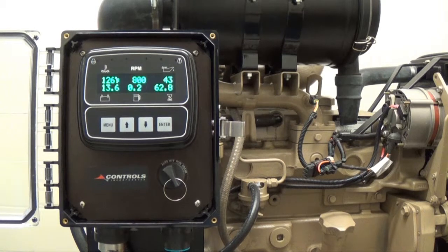In order to maintain a level of 300 inches of fluid in the well, the engine will accelerate to the maximum control speed of 1800 RPM if the fluid level is above 300 inches. Please note that when the engine ramps up or down, arrows will be shown next to the engine speed on the normal engine operating display.